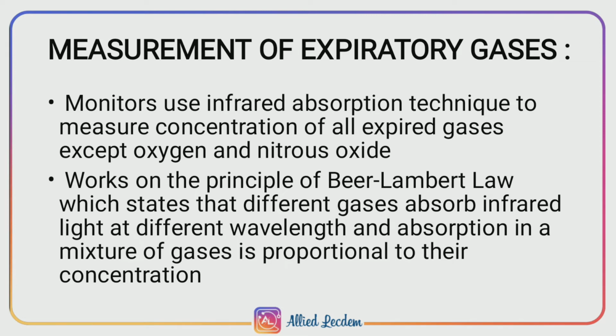These infrared devices work on the principle of Beer-Lambert law, which states that different gases absorb infrared light at different wavelength and absorption in a mixture of gases is proportional to their concentration.